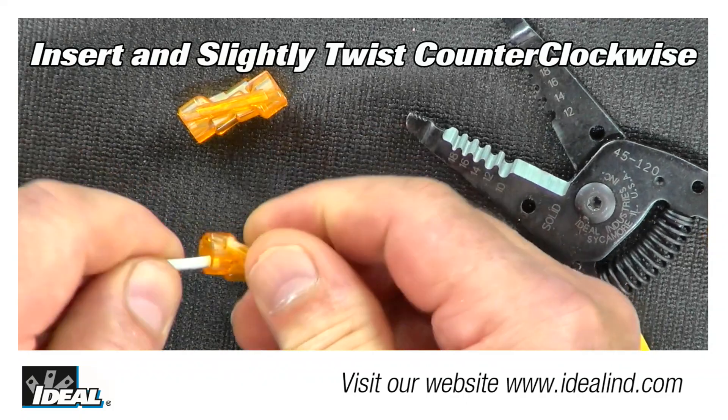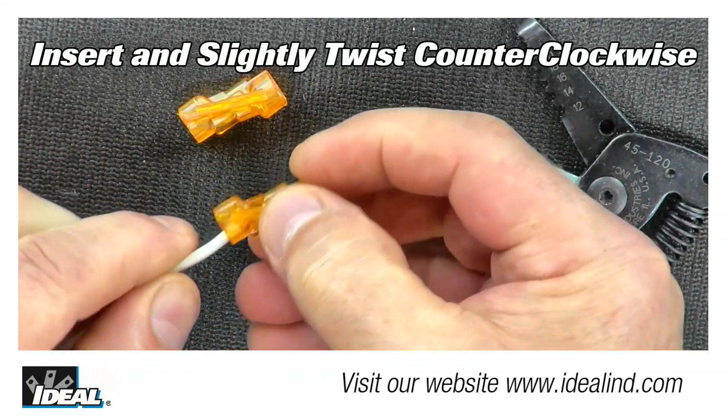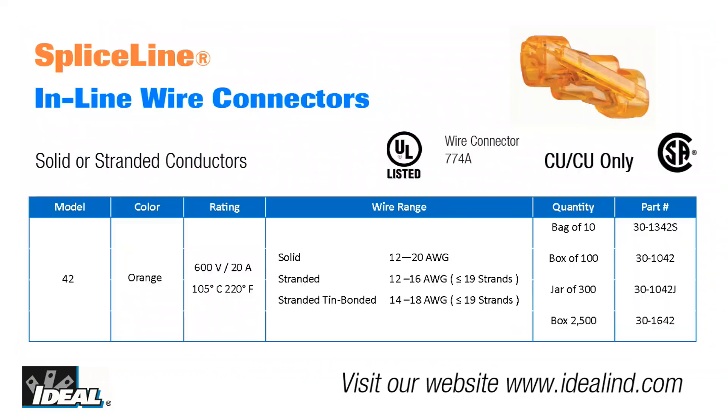Slightly twist stranded wire counterclockwise while inserting into the connector. If the stranded conductors are tin-bonded, the wire range is from 14 to 18 gauge conductors that are 19 strands or less.